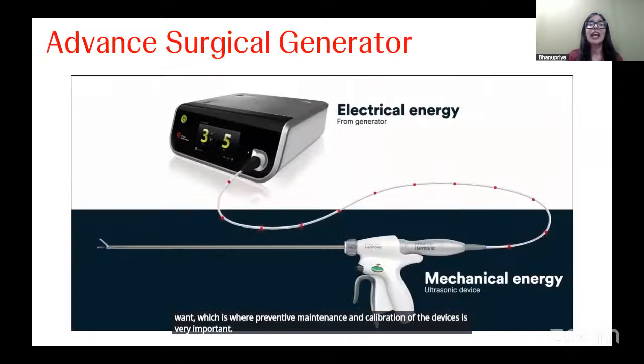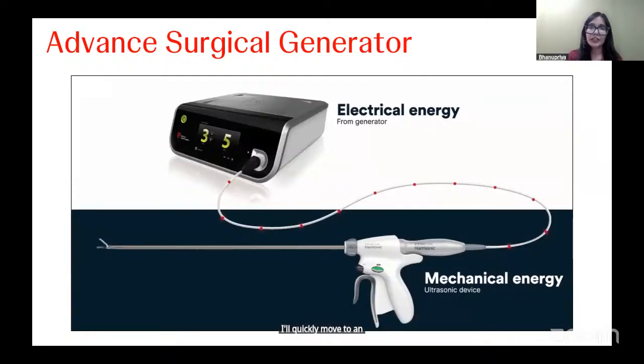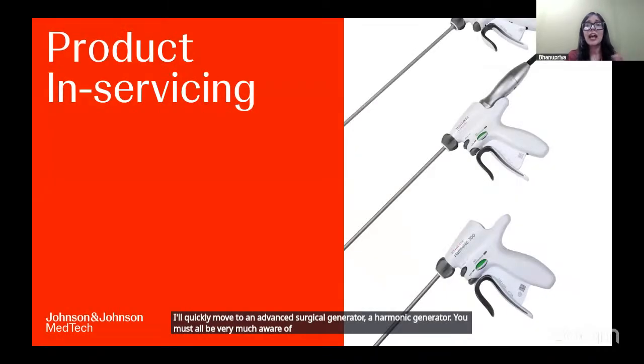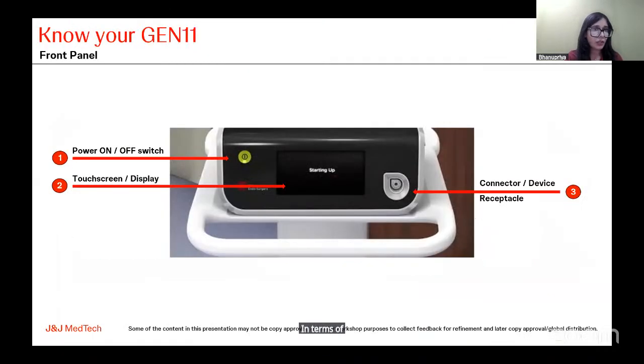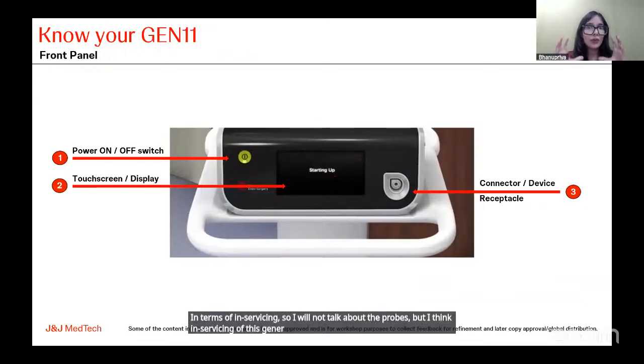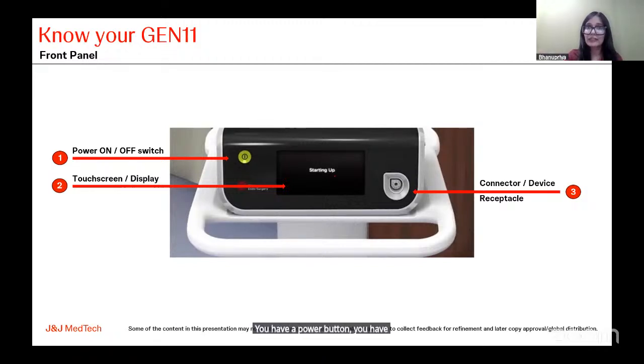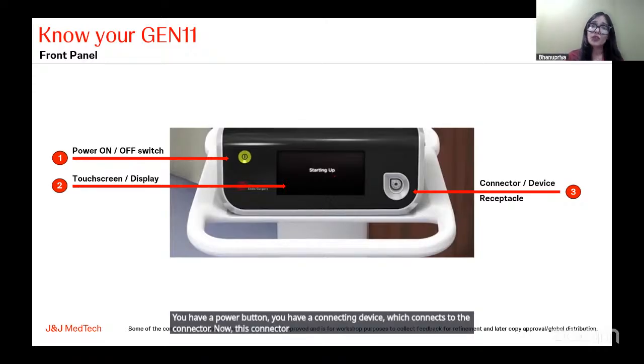I'll quickly move to an advanced surgical generator, a harmonic generator. You must all be very much aware of it. In terms of in-servicing, I will not talk about the probes, but you should know your generator inside and out. You have a power button, and you have a connector. A lot of people do not know it, but this connector connects both a harmonic as well as an advanced bipolar probe. So an Enseal or a harmonic, both will get attached to the generator.